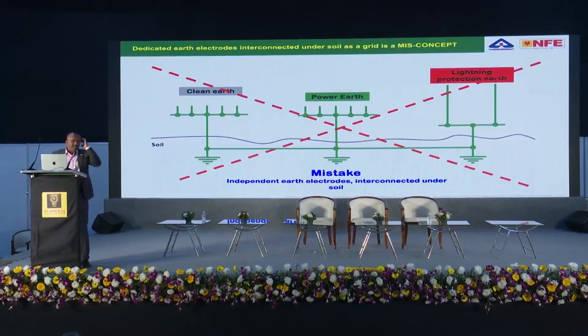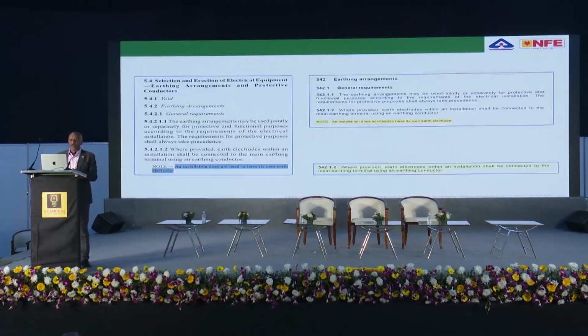In fact, in IS 732, which is again the IEC standard, I will show you the wording. You can read this particular clause, 5.4.2.1. Where provided, that means if provided, an earth electrode within an installation shall be connected to the main earthing terminal of that installation. You have a common bus bar. If you have an earth electrode, you connect it to that bus bar. That's it. And then there is a note: an installation does not need to have its own earth electrode. An installation means a building, let's say a hospital. That means your hospital doesn't need to have an earth electrode, but you need to have very good equipotential bonding.